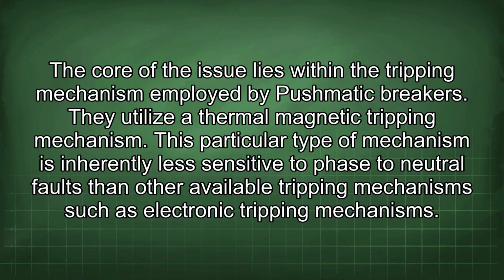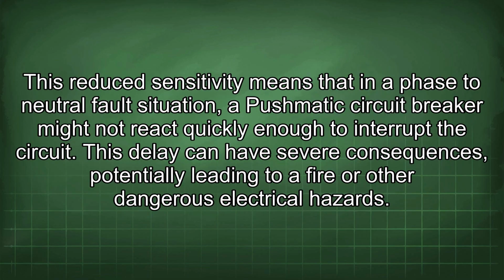The core of the issue lies within the tripping mechanism employed by Pushmatic breakers. They utilize a thermal magnetic tripping mechanism. This particular type of mechanism is inherently less sensitive to phase-to-neutral faults than other available tripping mechanisms such as electronic tripping mechanisms. This reduced sensitivity means that in a phase-to-neutral fault situation, a Pushmatic circuit breaker might not react quickly enough to interrupt the circuit. This delay can have severe consequences, potentially leading to a fire or other dangerous electrical hazards.